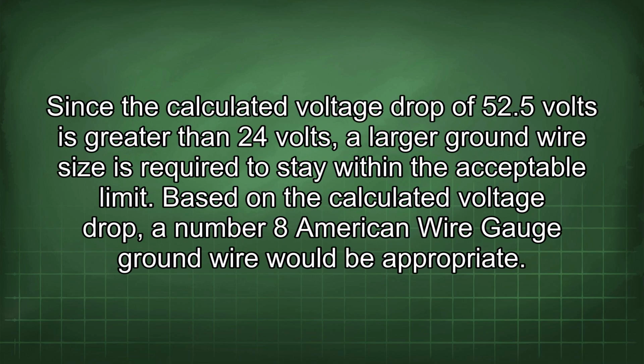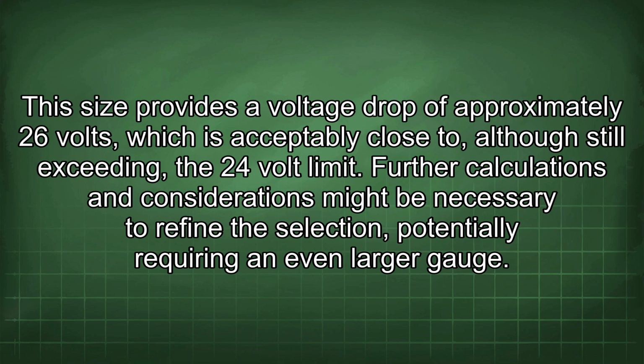Since the calculated voltage drop of 52.5 volts is greater than 24 volts, a larger ground wire size is required to stay within the acceptable limit. Based on the calculated voltage drop, a number 8 American wire gauge ground wire would be appropriate. This size provides a voltage drop of approximately 26 volts, which is acceptably close to, although still exceeding, the 24 volt limit. Further calculations and considerations might be necessary to refine the selection, potentially requiring an even larger gauge.